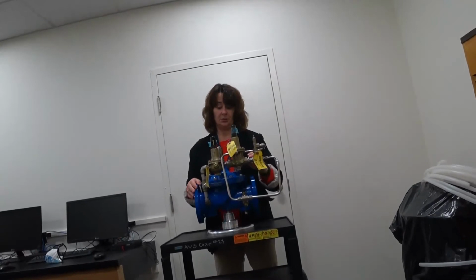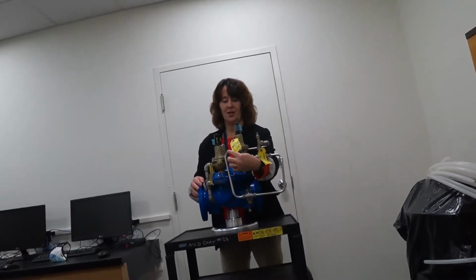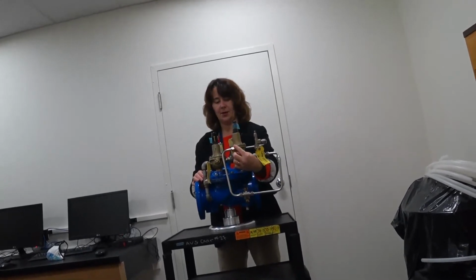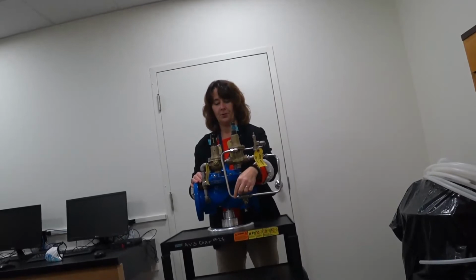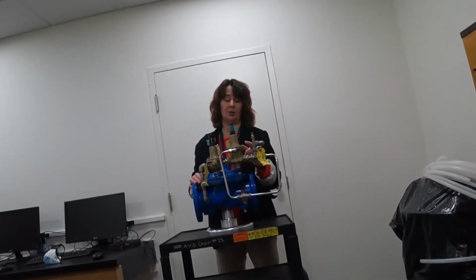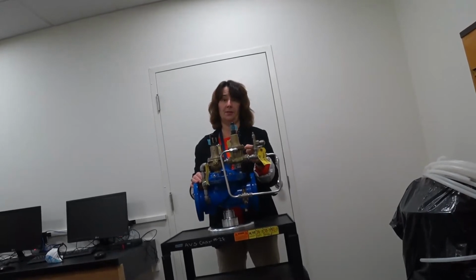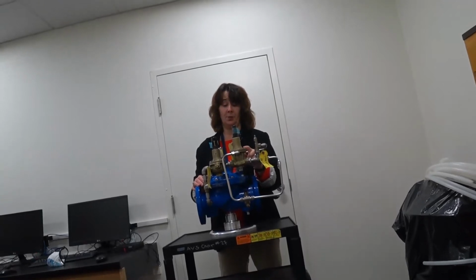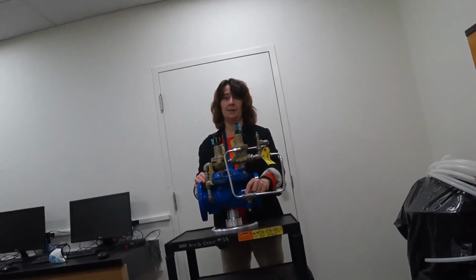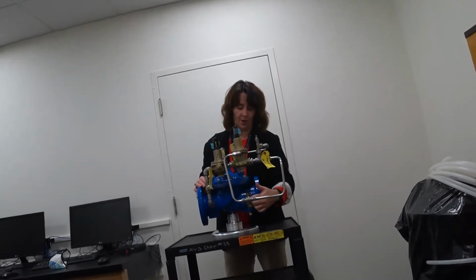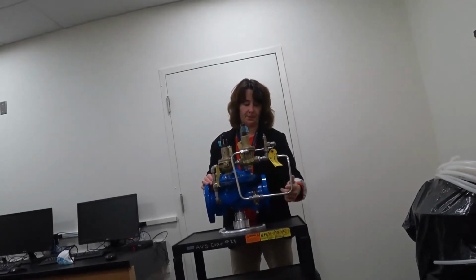So that's the choice. Now you'll notice here I've got this extra line which I haven't talked about, okay? This line is not a line that water can flow through. All this line is, is a pressure sensing line. It transmits the pressure into the pressure sensing chamber on the CRD. That's its whole purpose. So the CRD will be open or closed based on what pressure it's sensing down here, okay?